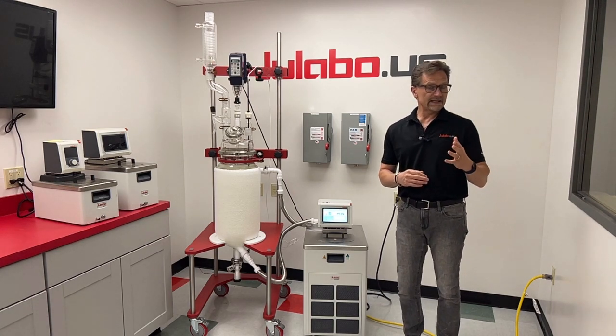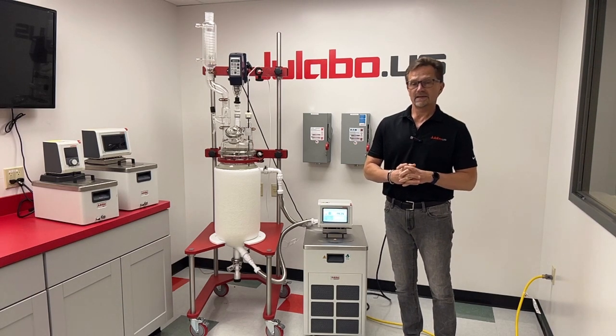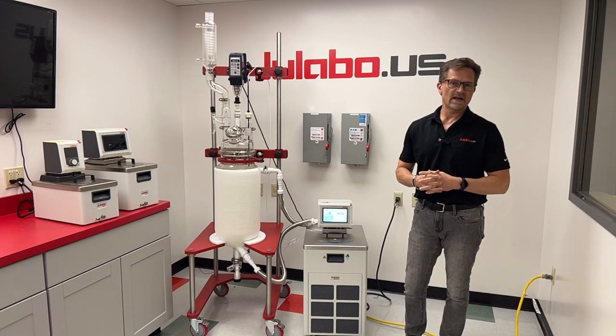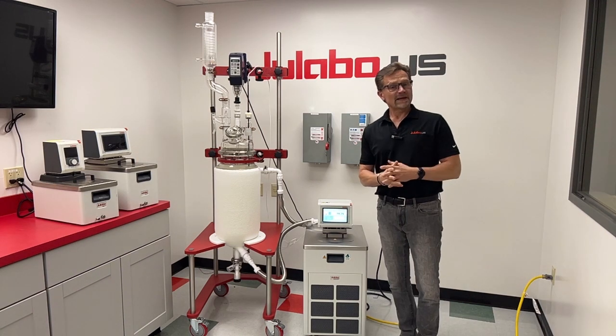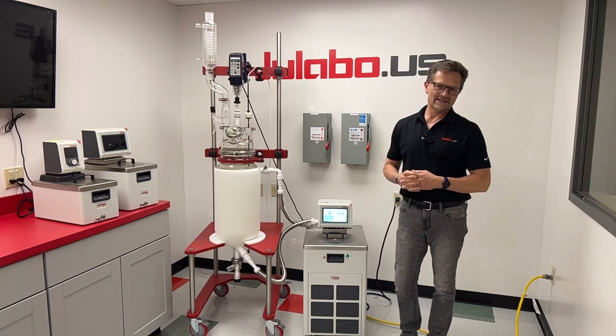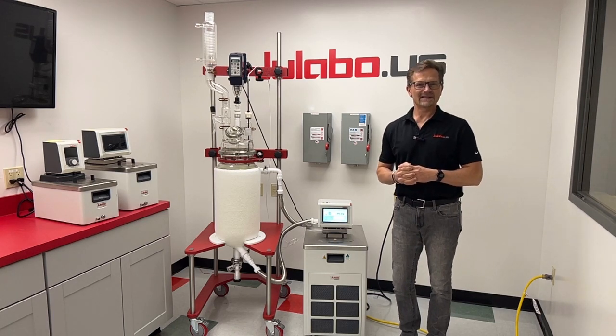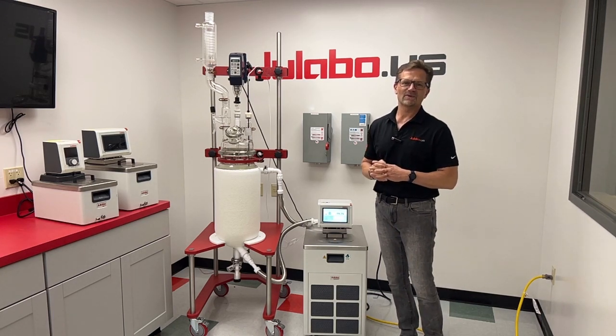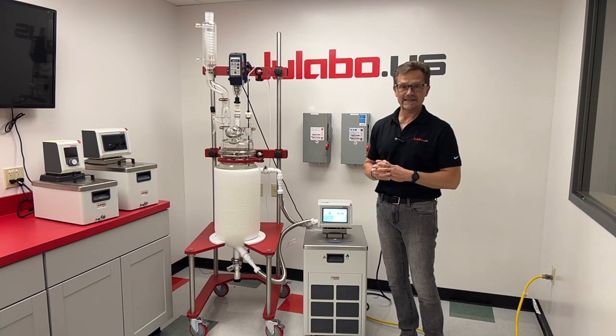The MX1800F has 1.8 kilowatts of cooling power at 20°C and 230 watts at minus 40°C. The MX2500F has two and a half kilowatts at 20°C, 850 watts at minus 20°C, and 300 watts of cooling power at minus 40°C, making it excellent for applications on 20 or 30 liter reactors.